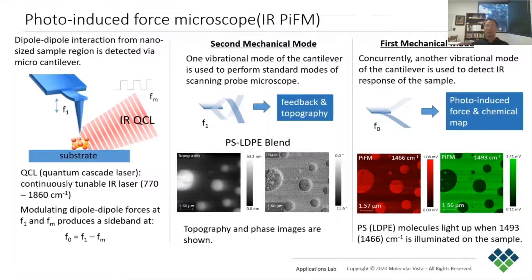In PIFM, we use two mechanical eigenmodes of the AFM cantilever as two independent force sensors to measure AFM topography and photo-induced sample response concurrently. In order to keep the tip close to the sample surface, we operate the AFM with a small drive at the second mode, F1, which has a force constant in excess of 1000 N per meter.